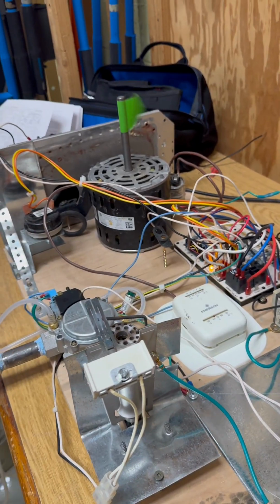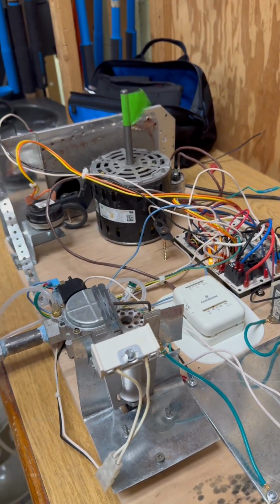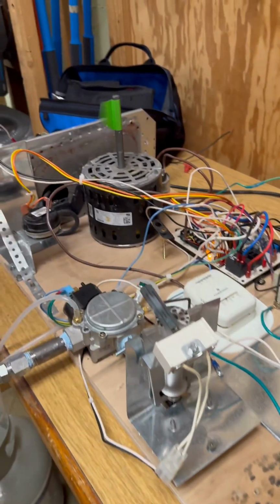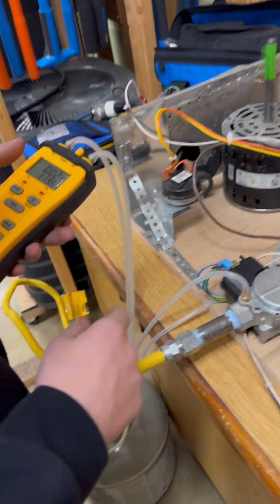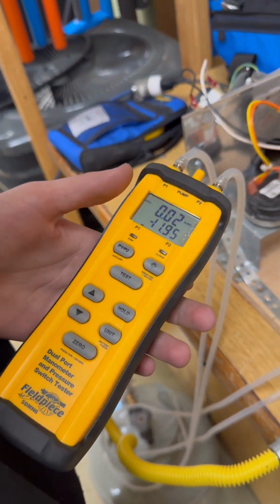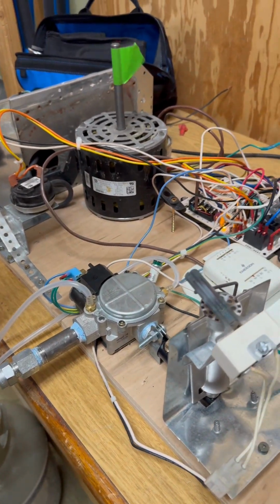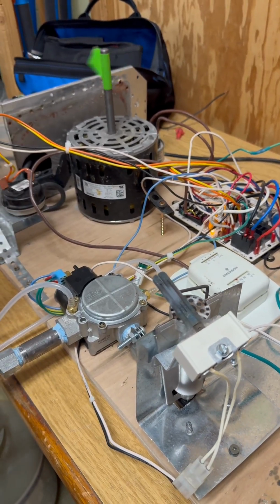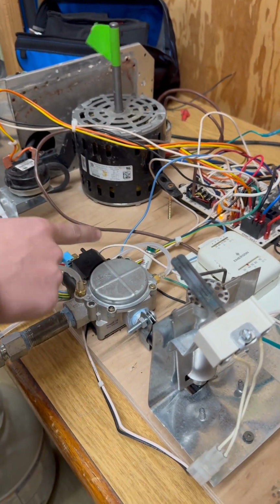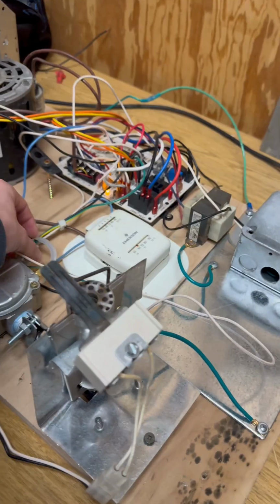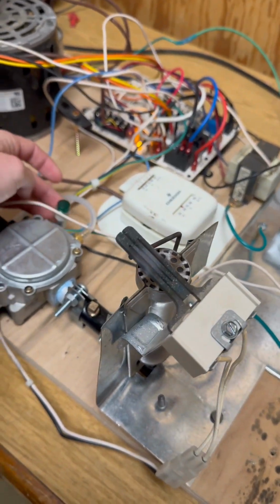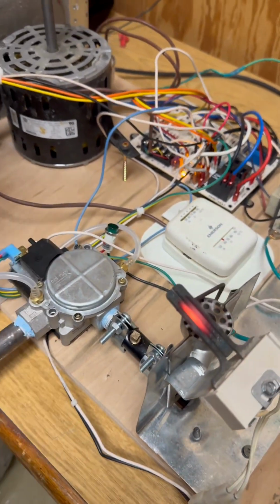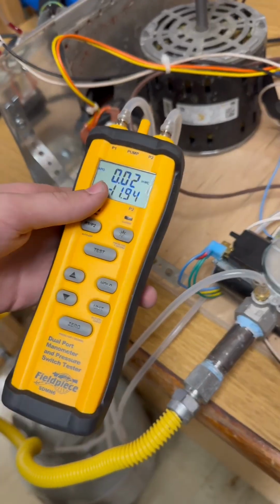Alright, so our blower just stopped. It was on a 90-second timer, so we had to wait for that. So now we're going to be watching our manometer while we go through the process of starting. And we're going to wait to see if our pilot light turns on, and our manometer should show about 3 inches of water column. So we have our igniter going.